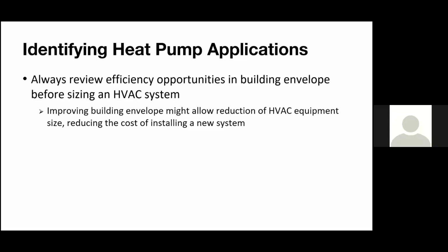The way electrification is going, and the meeting I was on with Boston coming up with their electrification plan, it was kind of in steps. And some of the steps, or recommended steps, were look at your envelope first, fix that, and then start to look at your cooking and domestic hot water, what's feeding that. And then your ventilation system, is that using natural gas? And then lastly, your heat pump systems in general. Okay, or your electric systems, what are you using for heating or cooling?